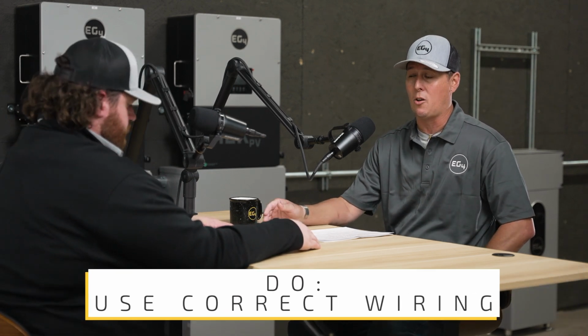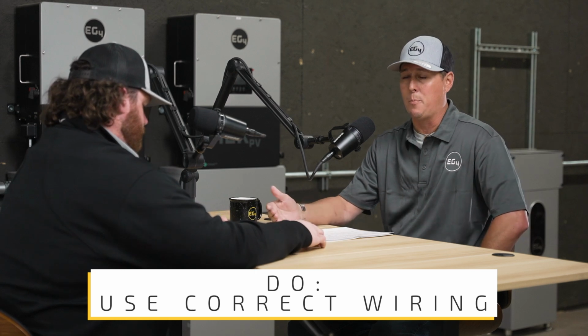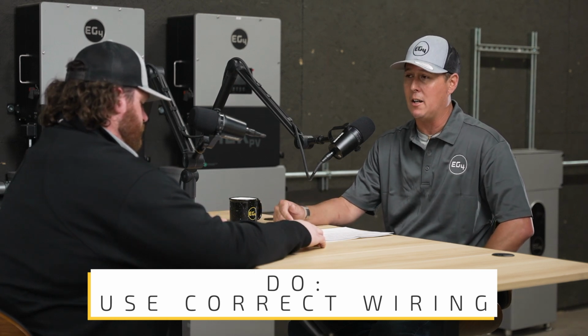Another big issue we see is utilizing correct wire sizing. You can go on Google and type in your amperage rating or DC voltage and it'll identify the correct wiring size. Unfortunately guys in the field may not have the correct wire size and they'll put in the next best thing, which can cause issues with the install. You could melt a wire, have a breaker trip, or have an internal fuse or relay pop inside our grid boss or something like that. We've seen systems where guys installed it incorrectly or used the wrong wire ampacity, causing issues with our systems. This reverts back to the installation manual, which tells you the appropriate wire size for the amperage rating of the system you're installing.